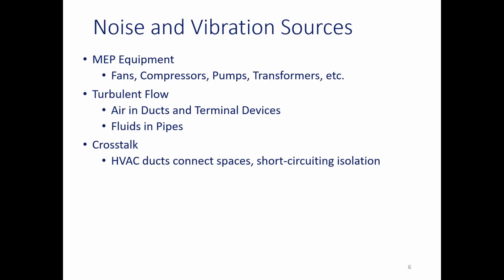And then another source or phenomenon that you should be aware of is crosstalk. This is where HVAC ducts connect spaces. So you might have one supply line that just goes over a row of offices, and each one has a diffuser that takes off and goes down to supply each room. Well, somebody talking in one room, that sound goes up, travels through the ductwork, and comes down in the other. That particular case isn't so bad, especially if you have some lining or some flex duct that connects the ductwork to the diffuser. Likely not a problem.